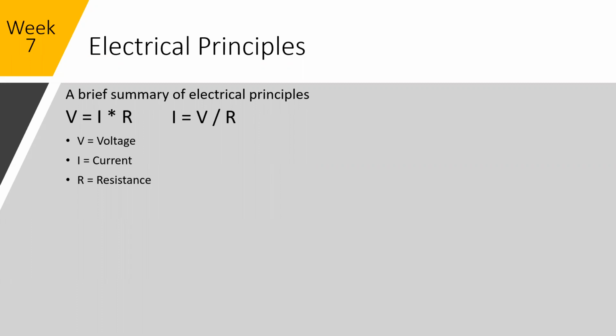It's important to know what the voltage is that they're using, what's the resistance, what's the rating of those parts, what's the current that we need to protect it with. So when you're sizing your breakers or your fuses, you want to make sure that you're not putting in a fuse that's 10 times what's going to be drawn, because it's far better to size it properly and blow a $5 fuse than damage a $10,000 piece of equipment. So, very basic stuff.